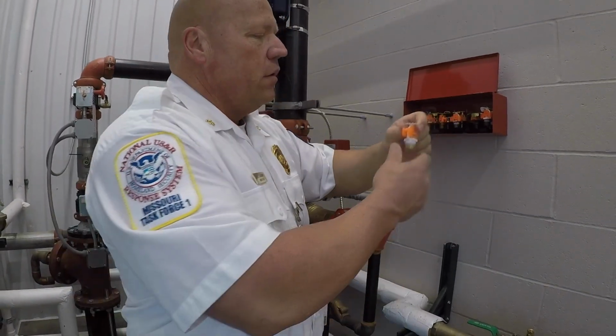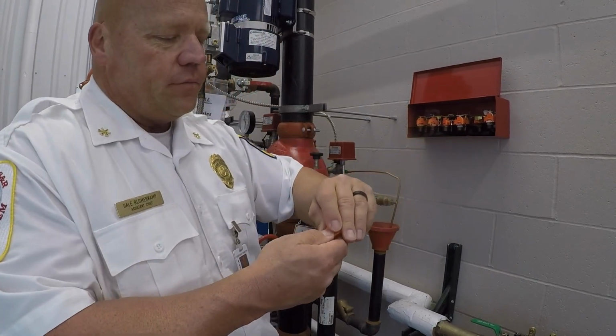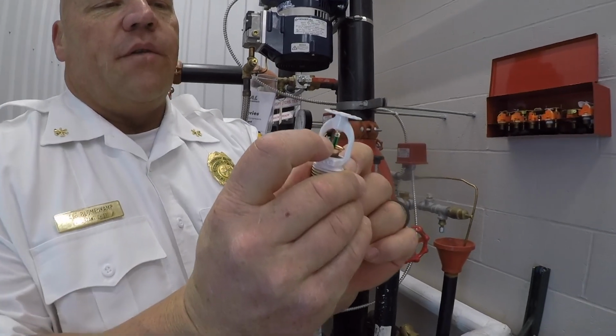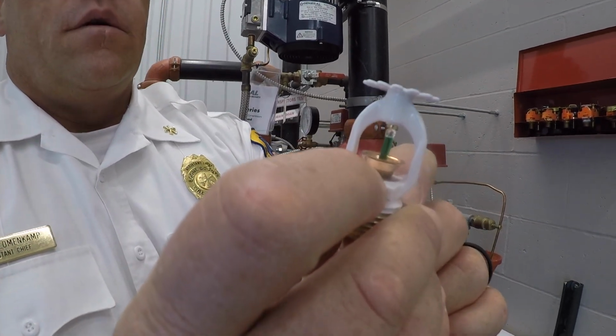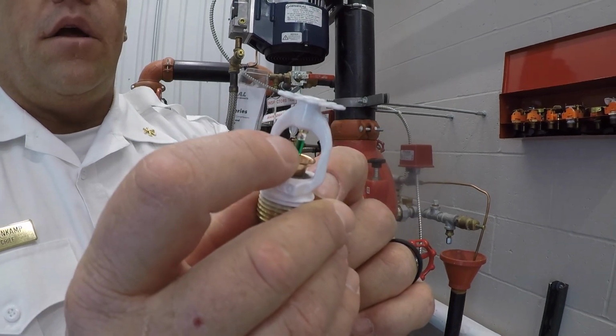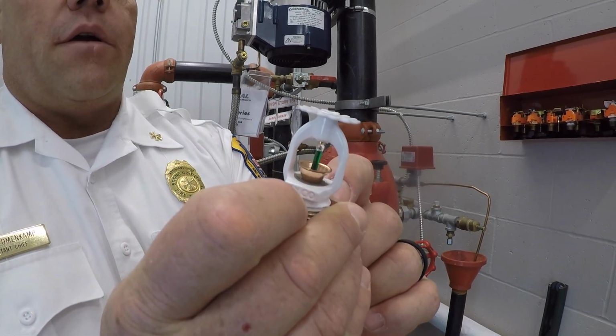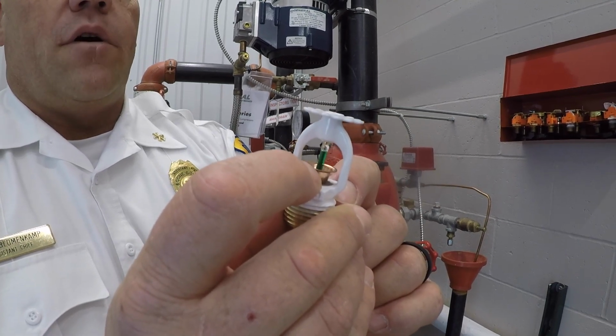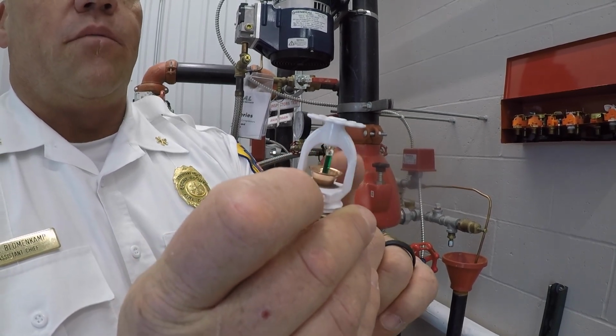We have white sprinkler heads that have a glass filament. Inside that filament is alcohol, so it's activated by heat. So once this sprinkler head, being green, reaches 200 degrees Fahrenheit, that glass ball breaks, this copper piece right here falls out, and water flows through the sprinkler.